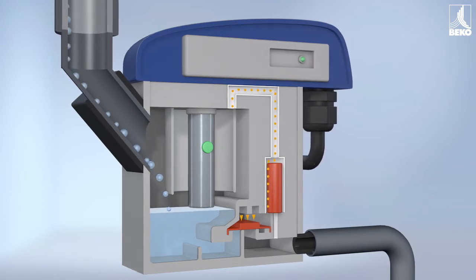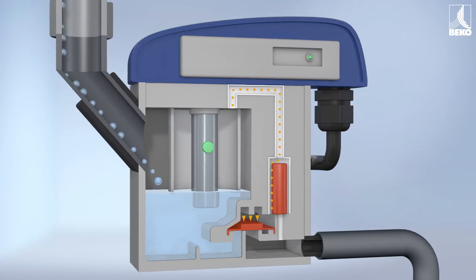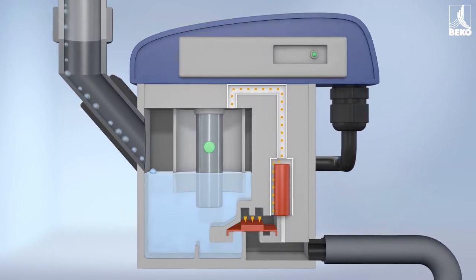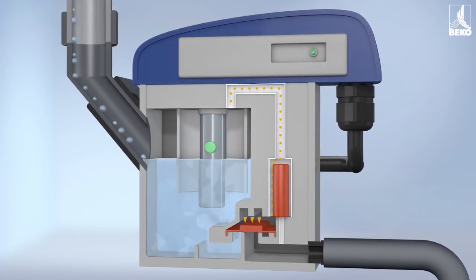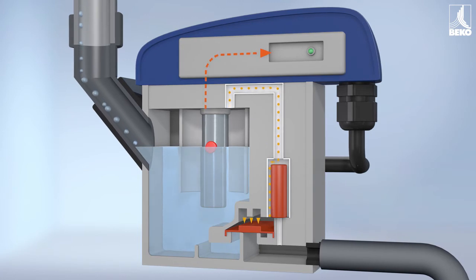Once again, as the condensate flows in, the membrane remains closed due to system pressure. Its larger upper surface provides the necessary closing force on the valve seat and seals it tightly. When the BEKOMAT is full, the solenoid valve is activated.